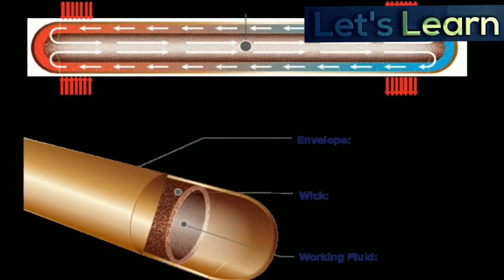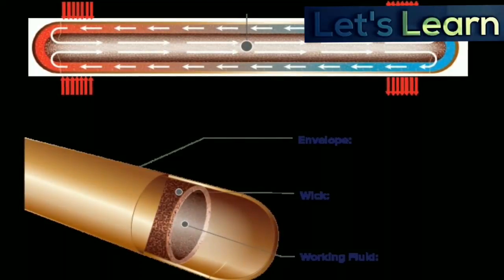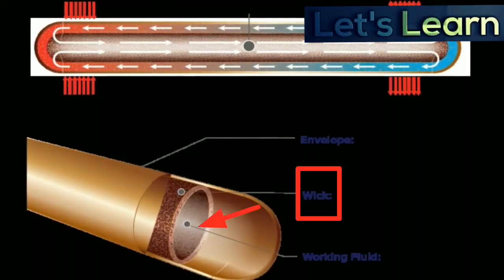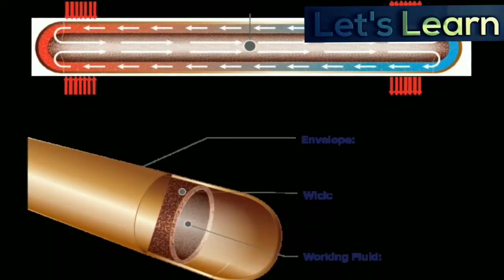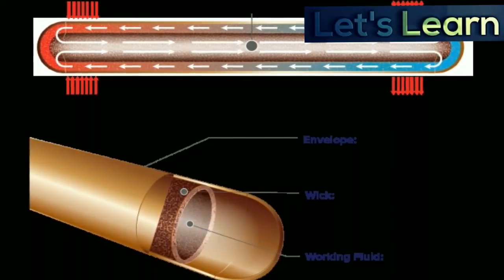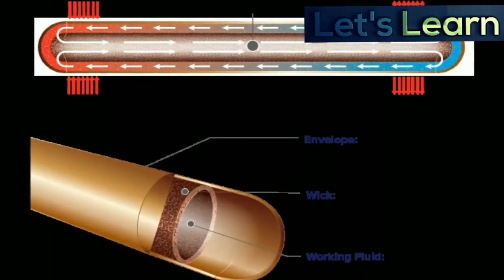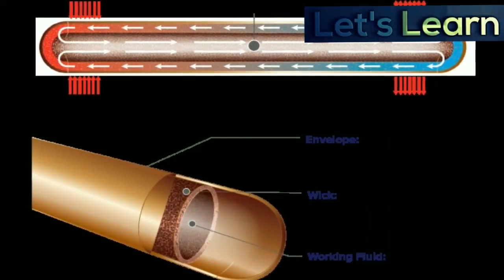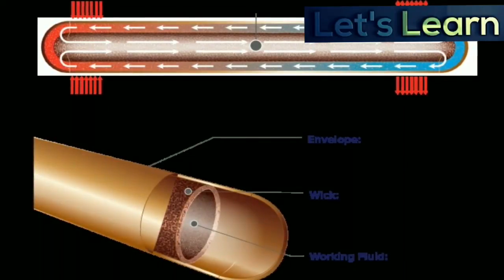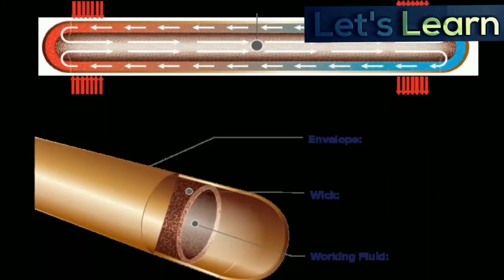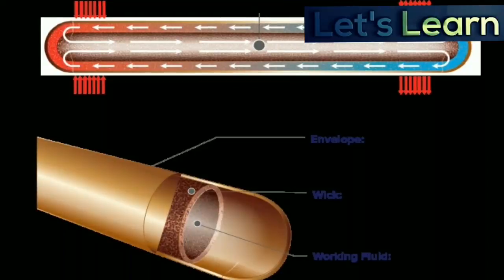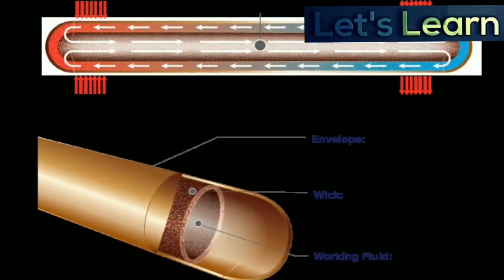In a standard heat pipe, the condensed liquid is returned to the evaporator using a wick structure, exerting a capillary action on the liquid phase of the working fluid. The wick structures used in the heat pipe include sintered metal powder, screen, and grooved wicks, which have a series of grooves parallel to the heat pipe axis. When the condenser is located above the evaporator in a gravitational field, gravity can return the liquid.